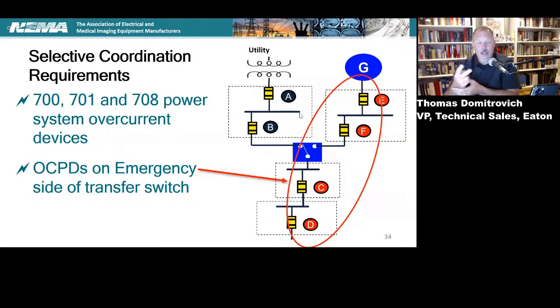So there are two aspects that are critical in determining selective coordination. You need to understand the characteristic curves, and you need to compare current. What the 0.1 second rule does is it basically ignores current. To achieve coordination in a 0.1 second world, you plot both curves, hide everything below 0.1 seconds, ignore the fault current, and make sure you have a separation of curves in the overload region. So all you know when you've done a 0.1 second analysis is that on an overload, the upstream device will not trip. You'll have coordination.